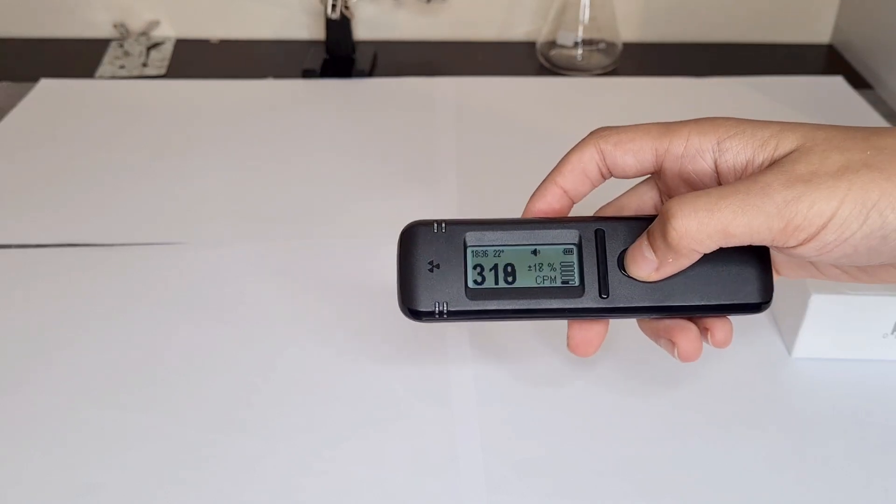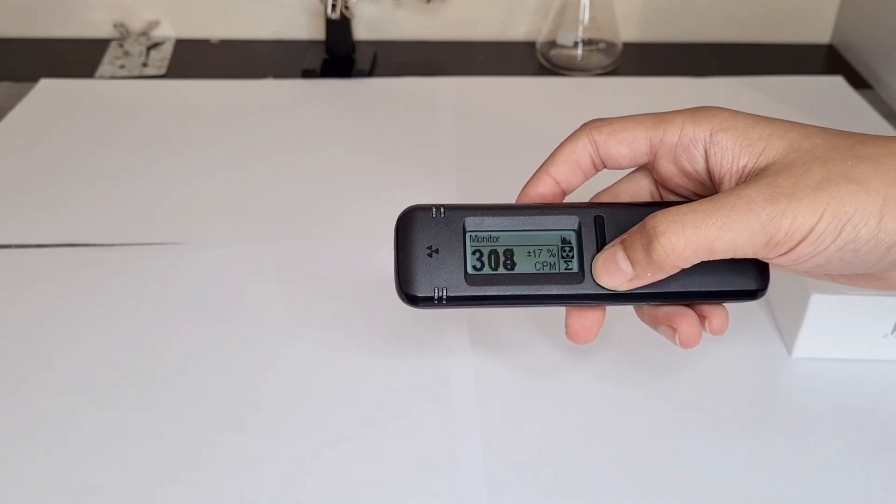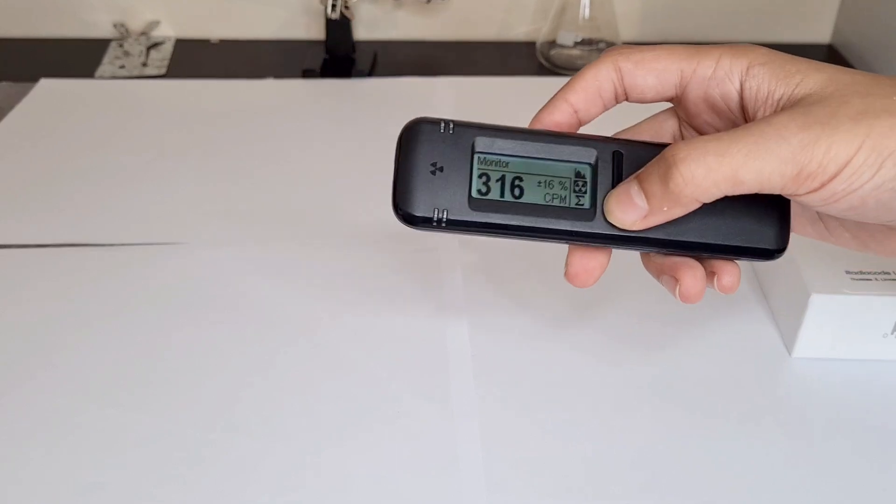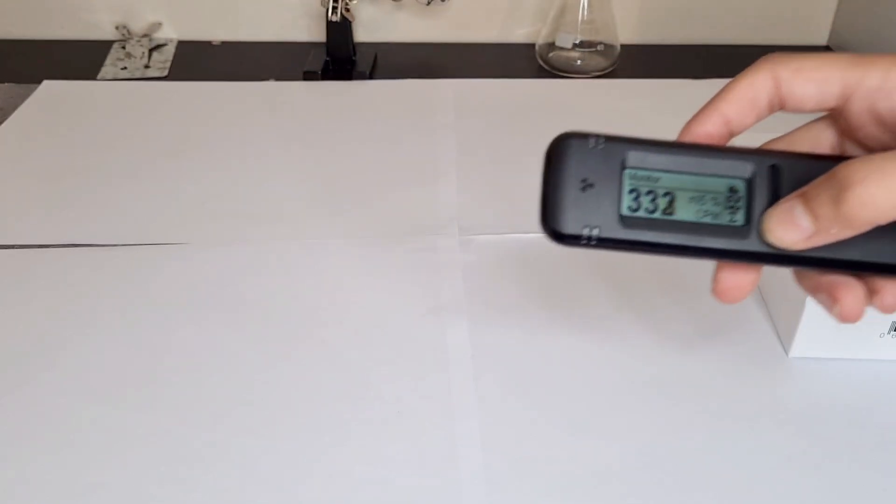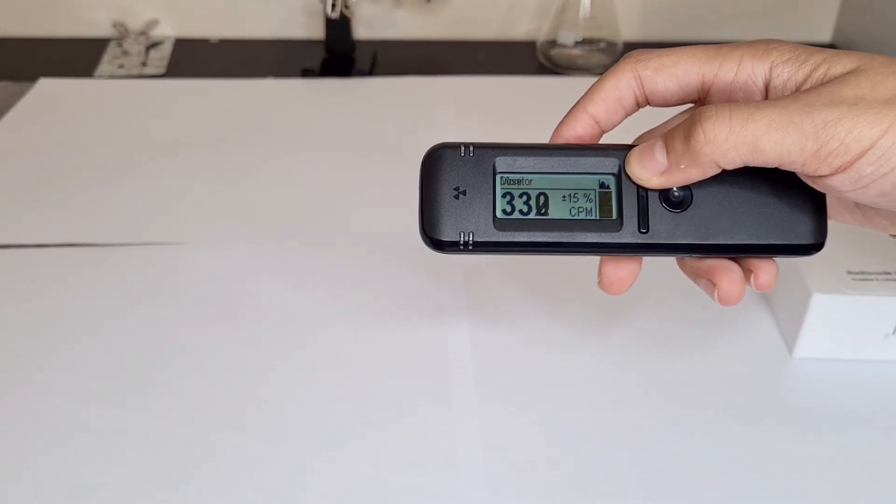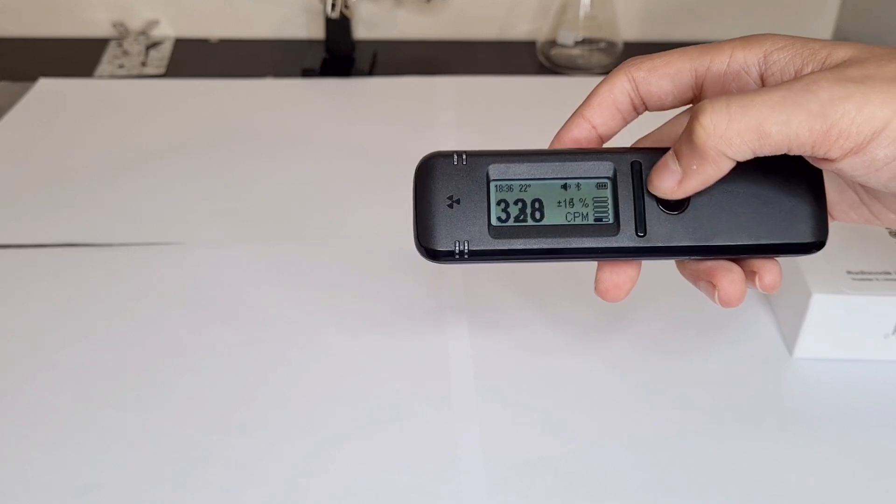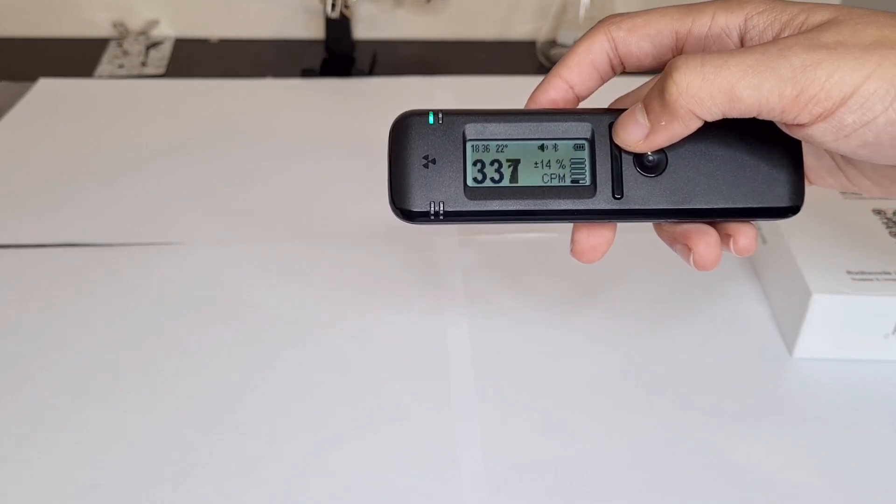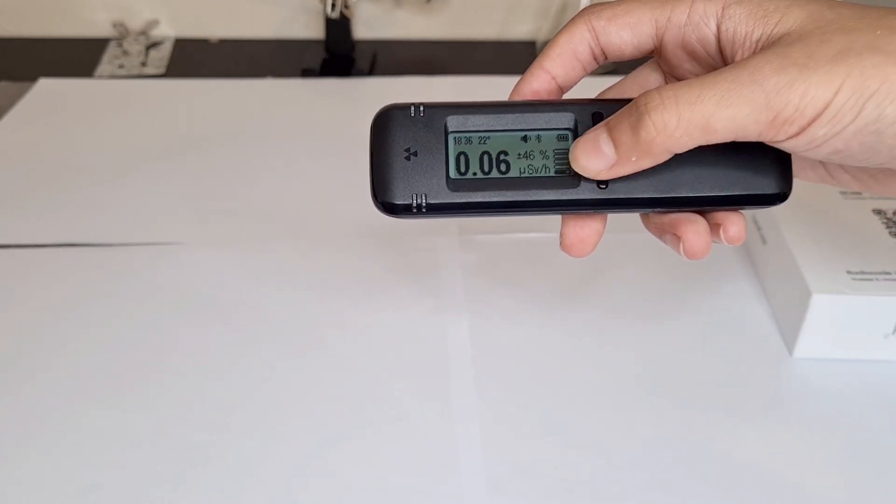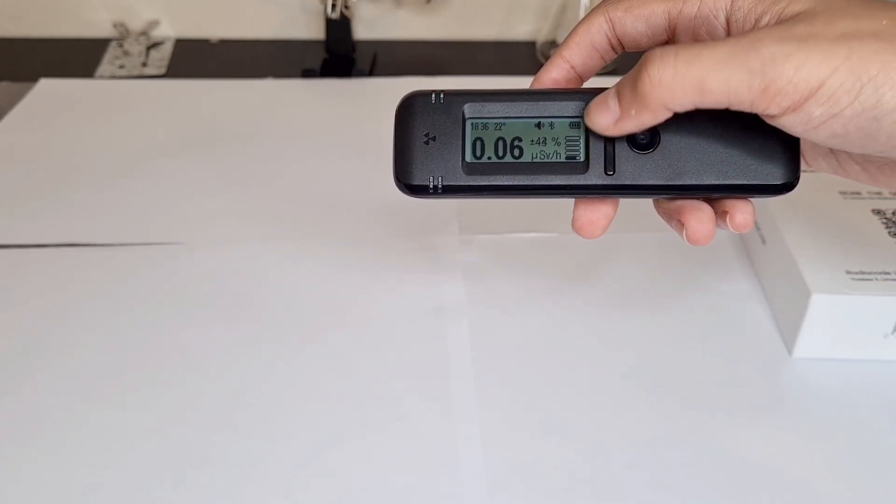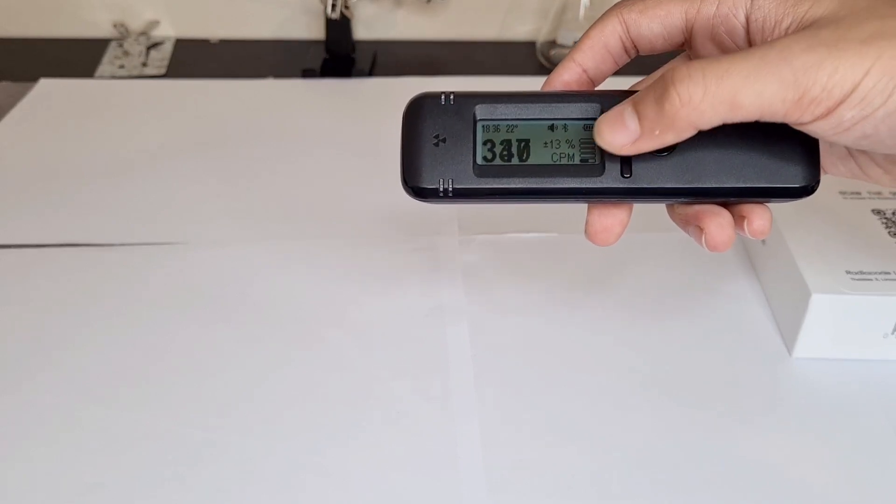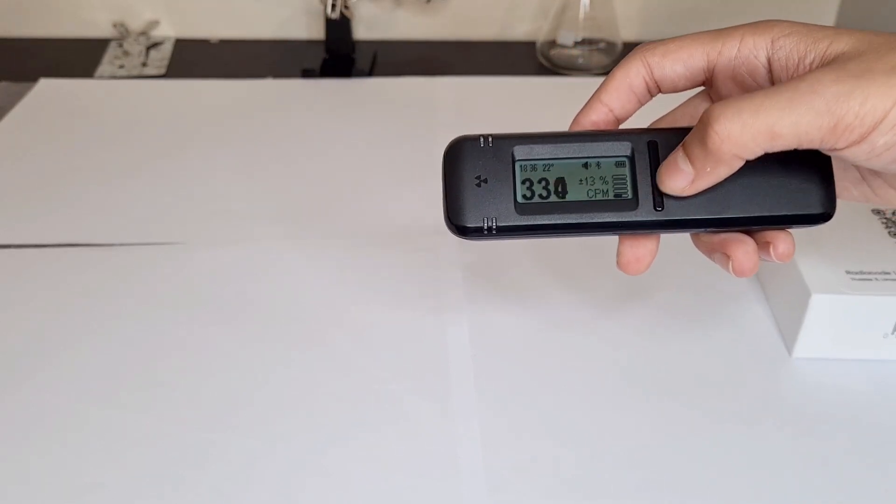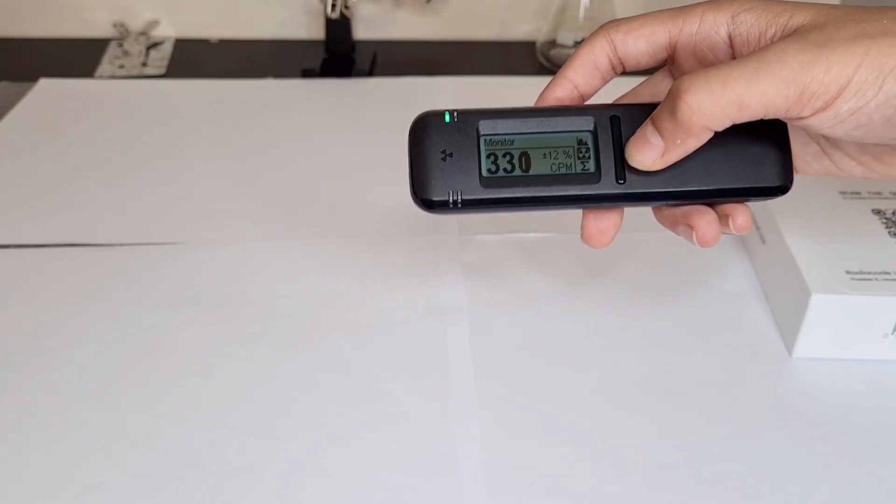Now this has more features than it looks like it does. Hold this down and that was just the sound of it connecting with something, aka my phone. Here's the monitor mode which I'm in right now. If you press up it gets you to microsieverts, aka dose rate.